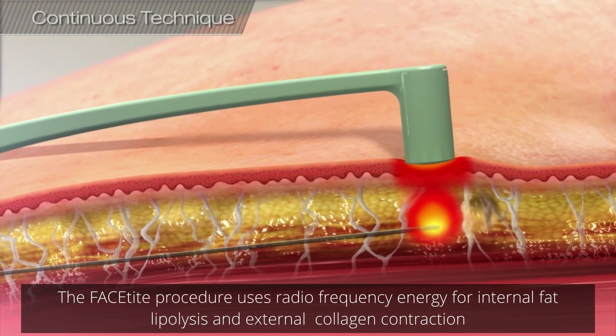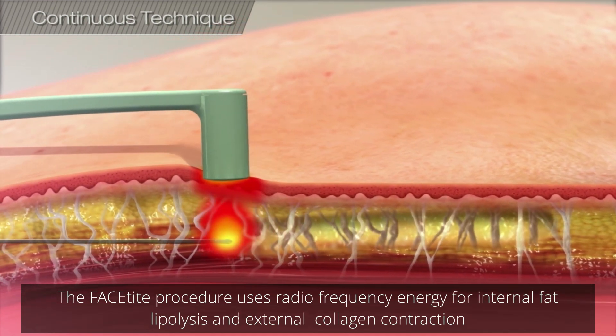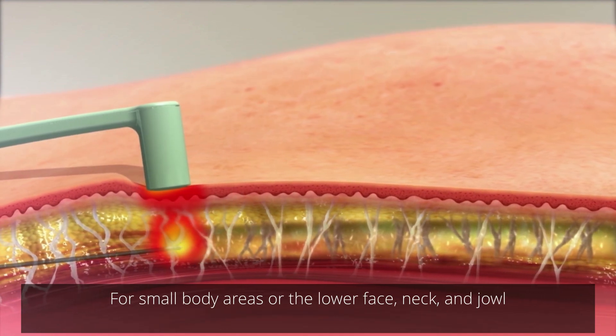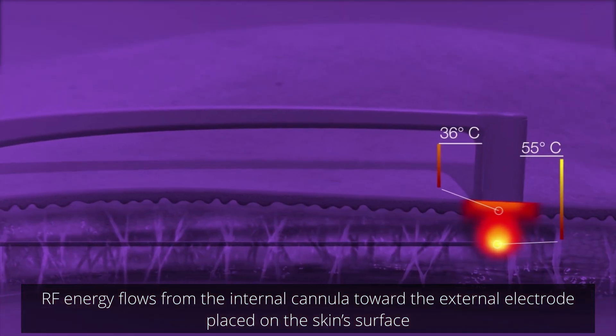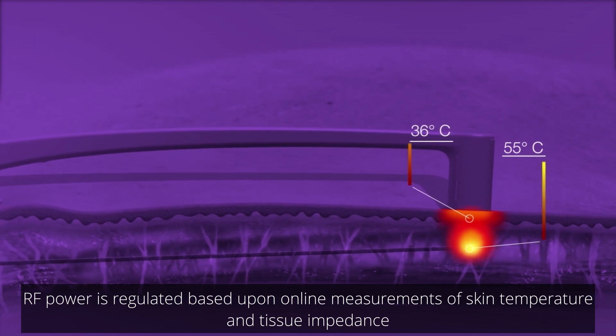The FACEtite procedure uses radiofrequency energy for internal fat lipolysis and external collagen contraction for small body areas, or the lower face, neck, and jowl. RF energy flows from the internal cannula toward the external electrode placed on the skin's surface. RF power is regulated based upon online measurements of skin temperature and tissue impedance.